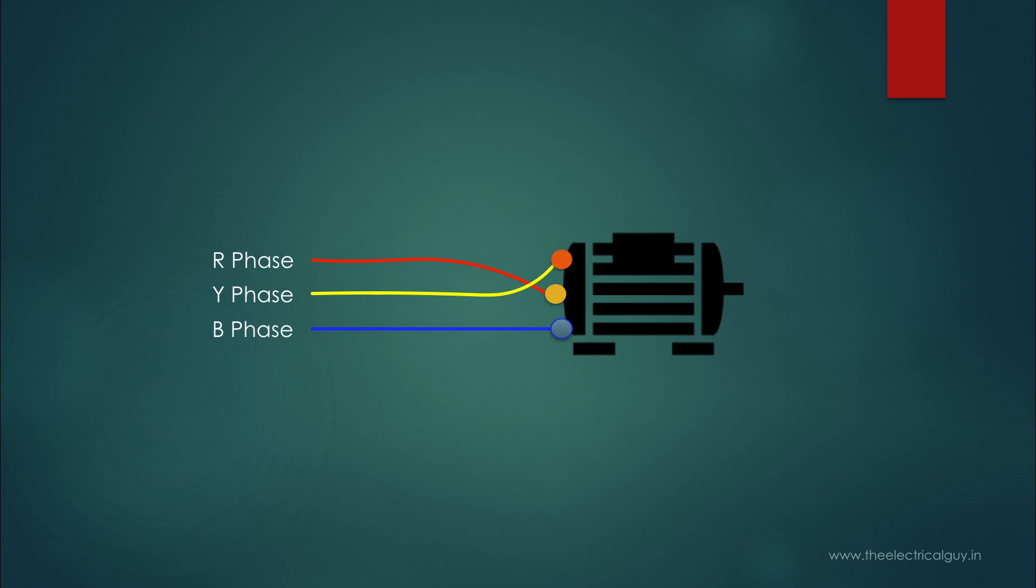Why is phase sequence important for induction motors? Because the direction of rotation of the motor can be changed with a change in phase sequence. So if your motor is running in the opposite direction, phase sequence could be one of the causes. If your three-phase load is purely resistive, then change in phase sequence will not affect anything. But it may affect unbalanced inductive or capacitive loads.